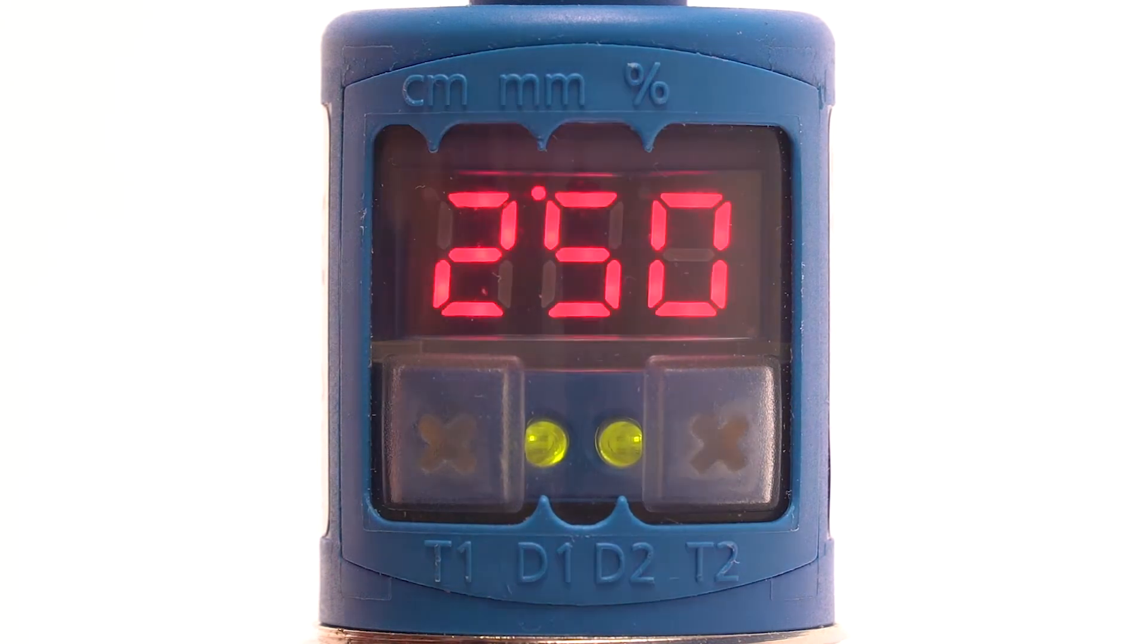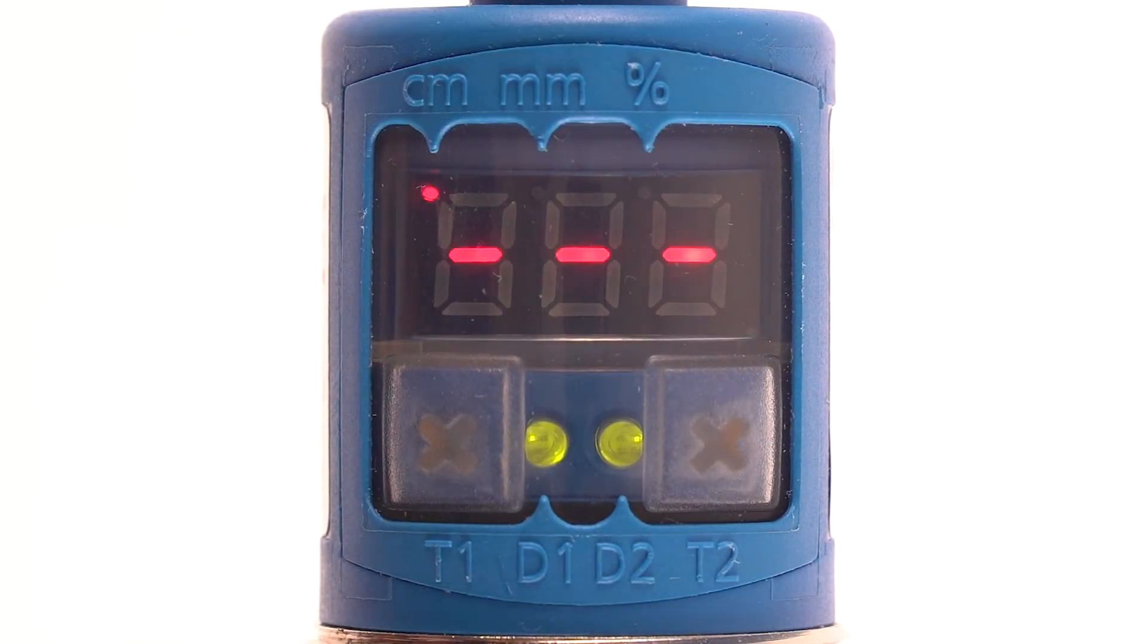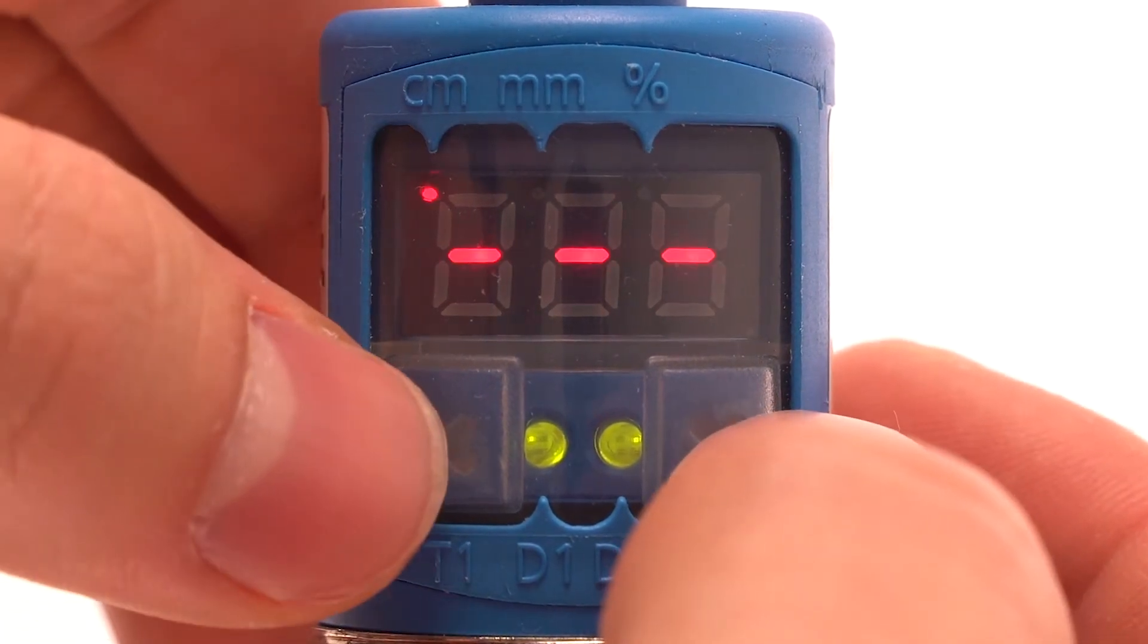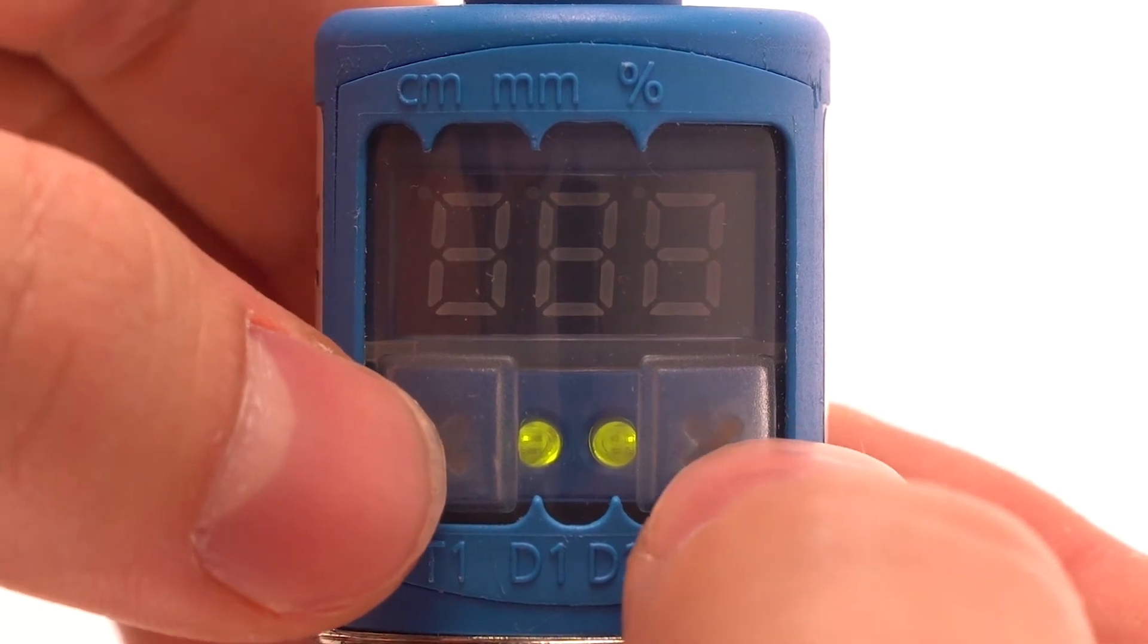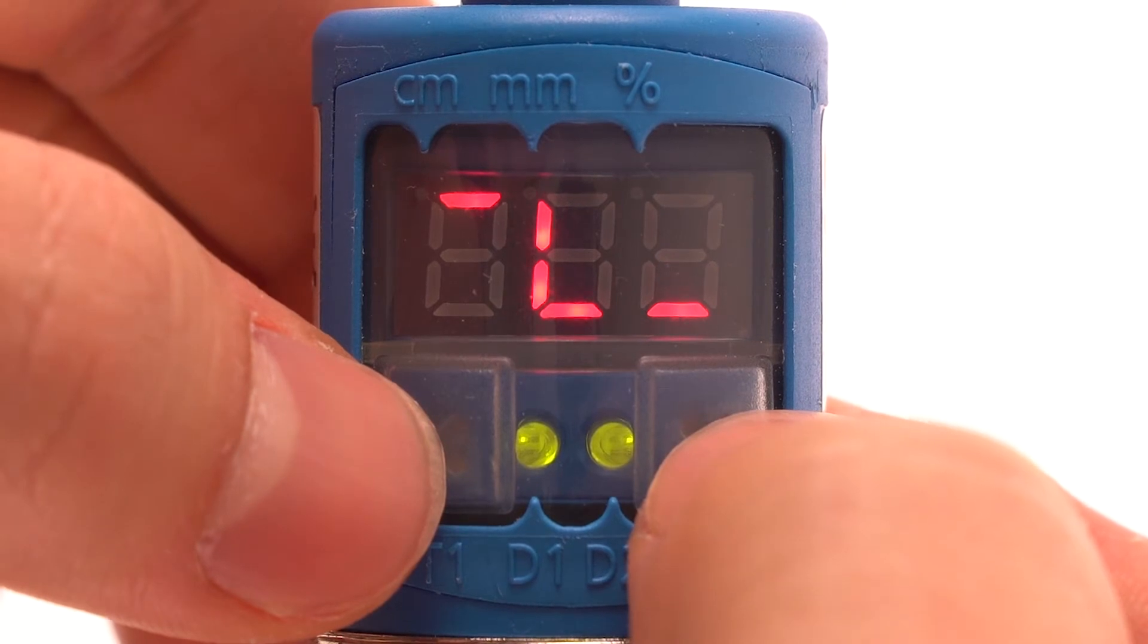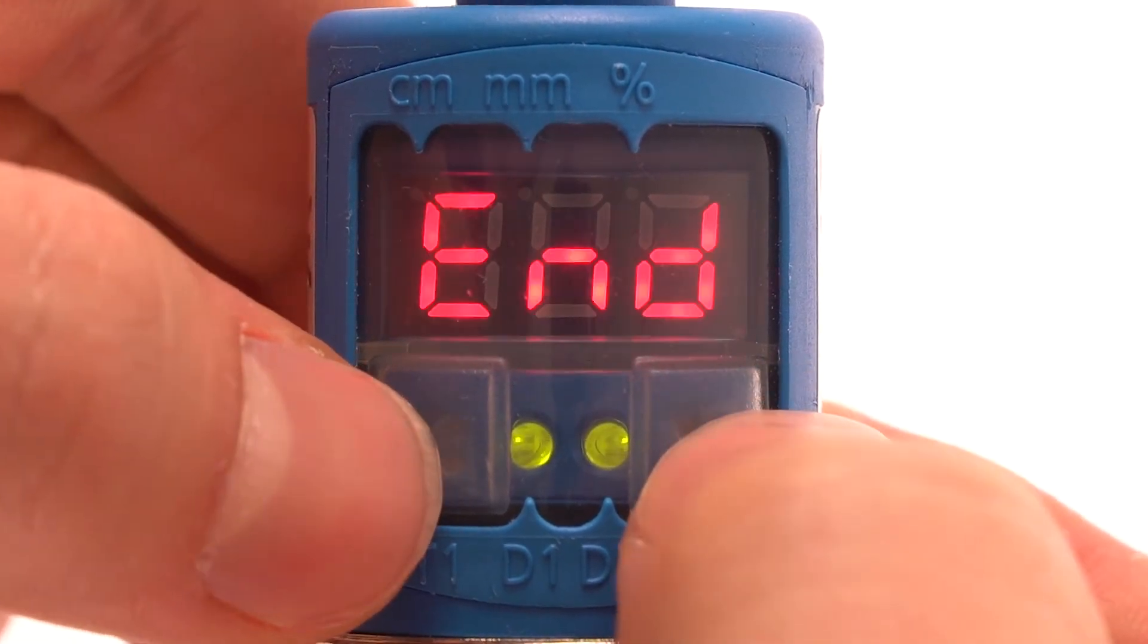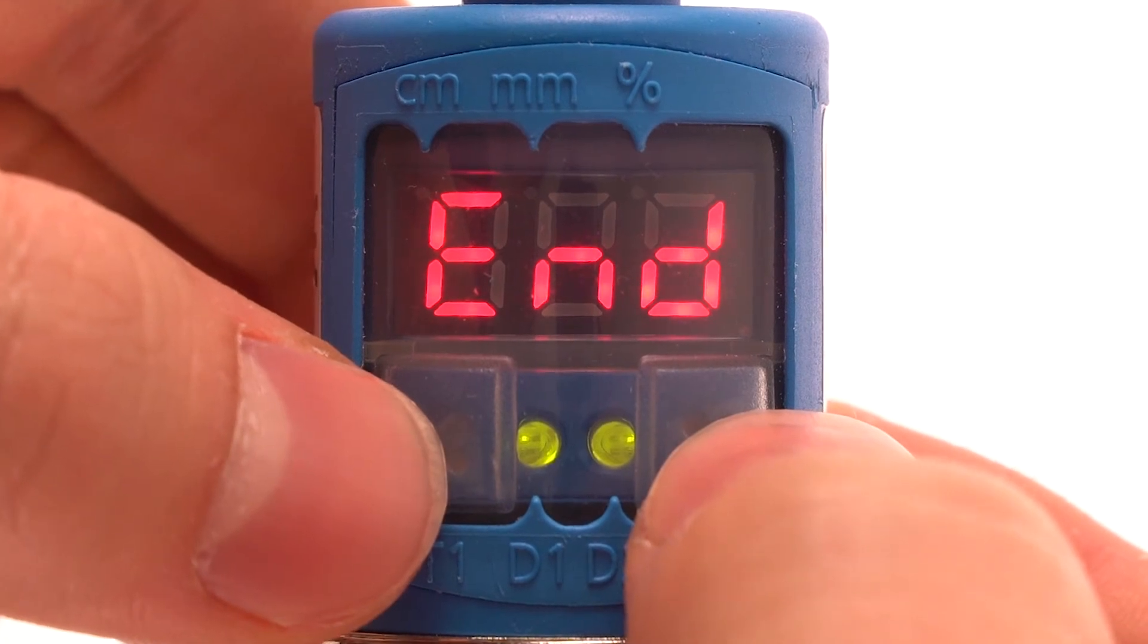Now simultaneously press T1 and T2. Three dashes appear on the display. For a simple switching point, simultaneously press T1 and T2. Select the normally closed, normally open contact. Simultaneously press T1 and T2 until end appears.